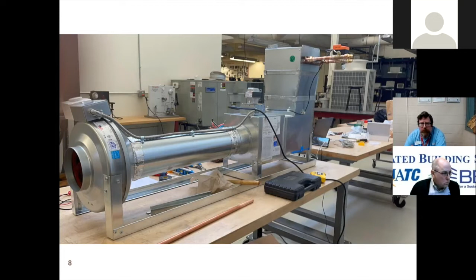This is just a different view, an end view. You can see the three-way valve a little better, piping into the reheat coil. I have unions on both sides of the reheat coil so I can disconnect that assembly, because it does stick out quite a ways. That makes storage a little easier, and it makes transportation a whole lot easier—I don't have to worry about knocking that off or bending the copper tubing on the coil and destroying it.